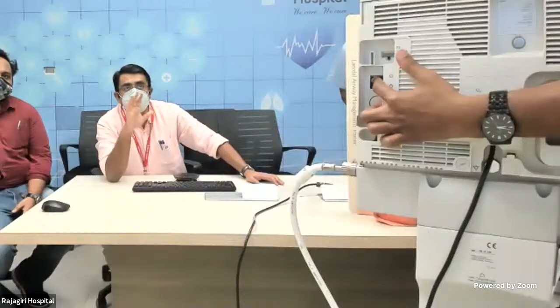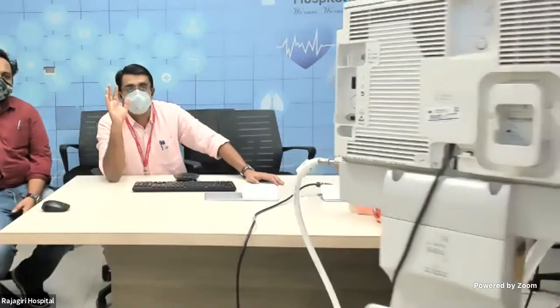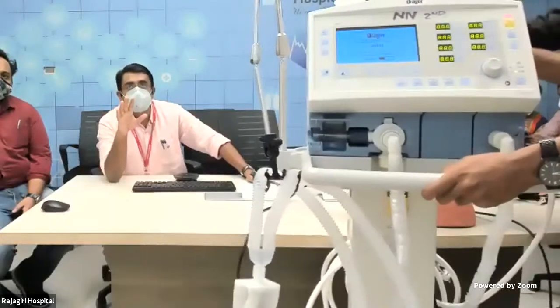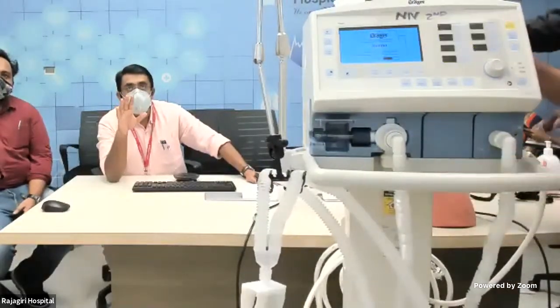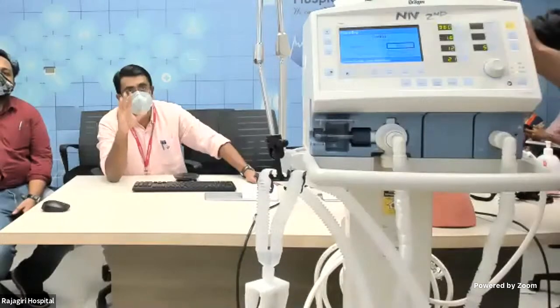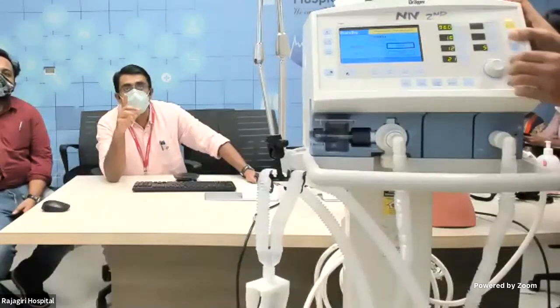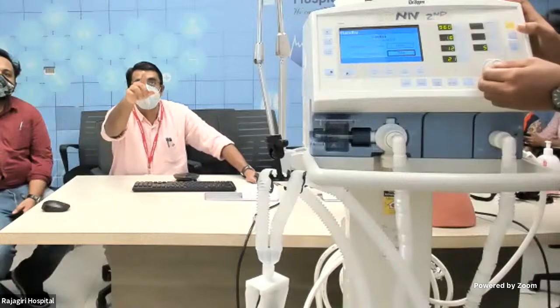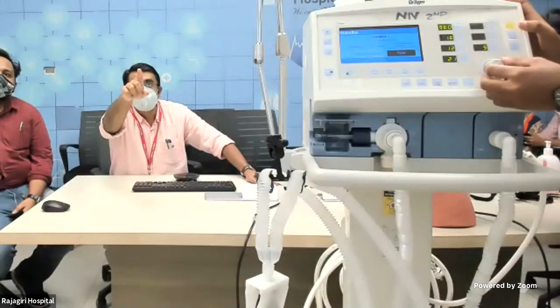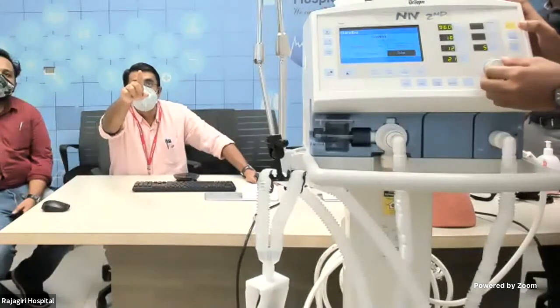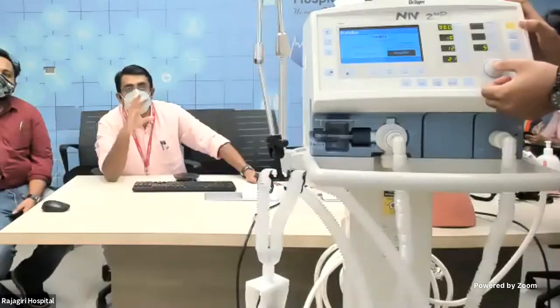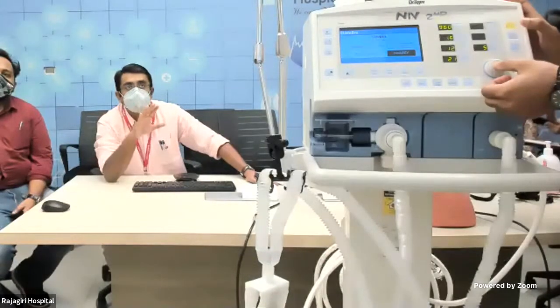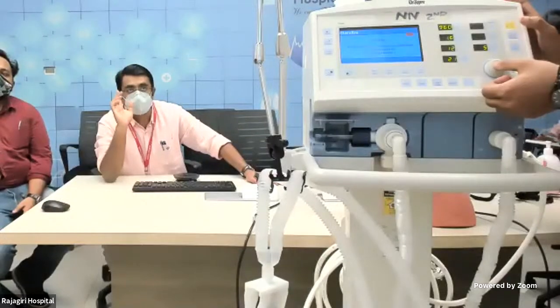There is a button over there, as in every machine, which you use to turn the machine on and off. When you turn it back on, there will be a screen showing the machine is starting. Once the machine is on, it will ask whether it is NIV mode or tube mode. You can see over here, the tube mode or NIV mode. Tube is the endotracheal tube, and NIV is the NIV mode, because both have slightly different mechanisms in the machine. It is important to select that, number one.